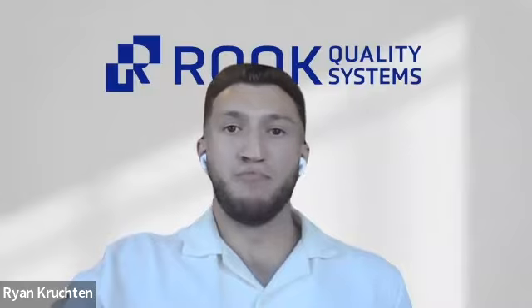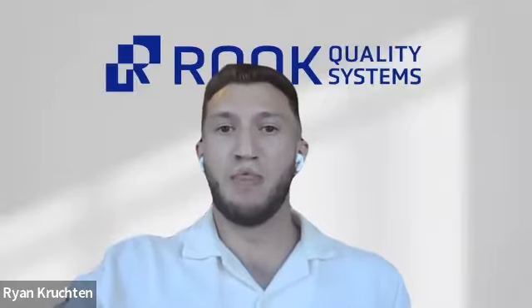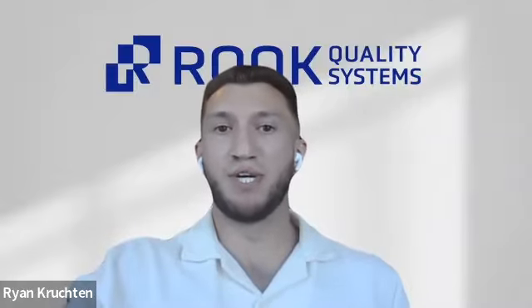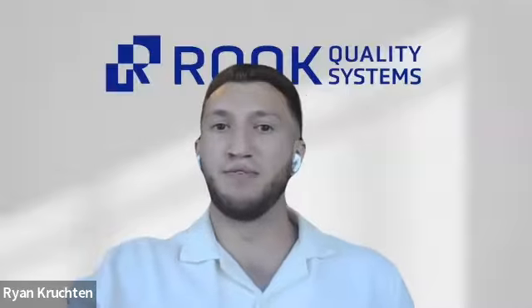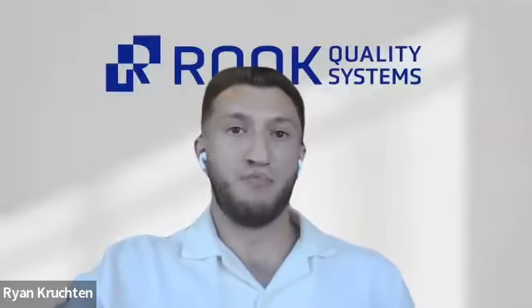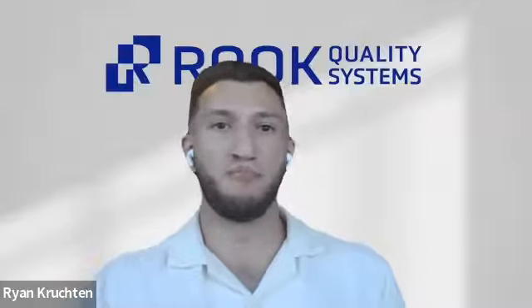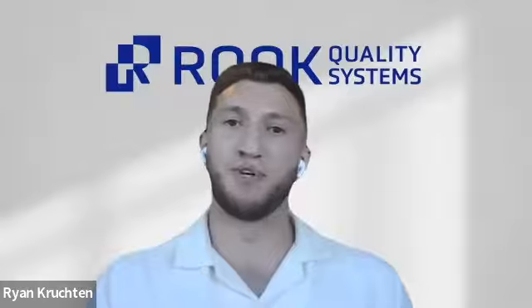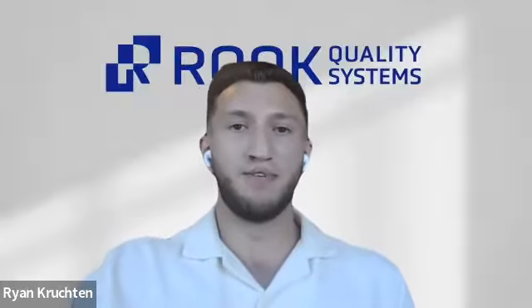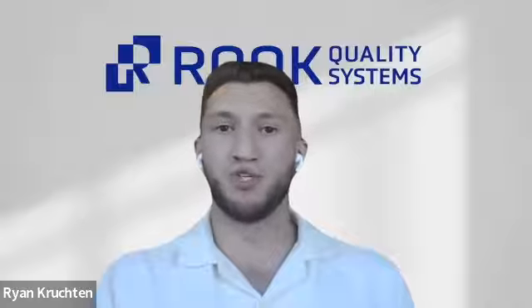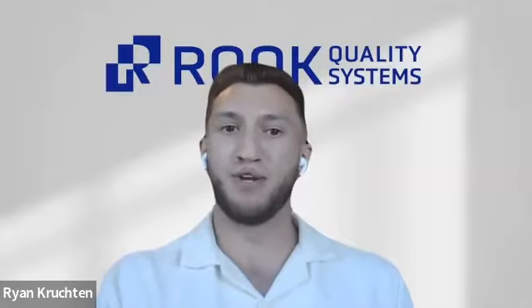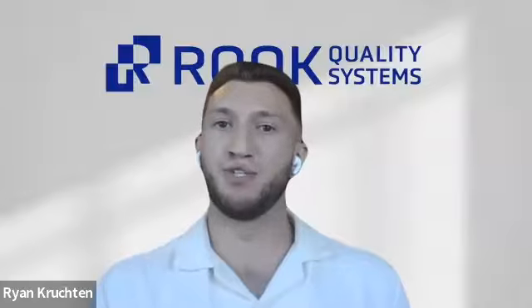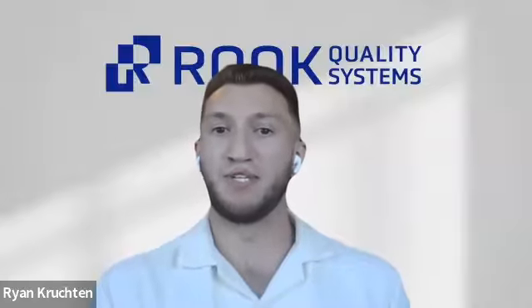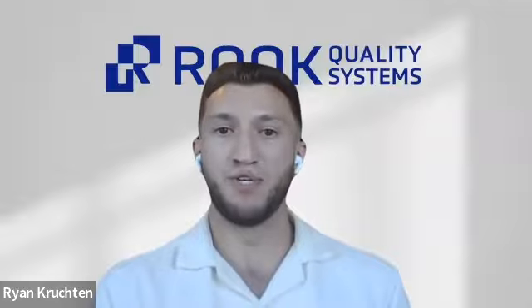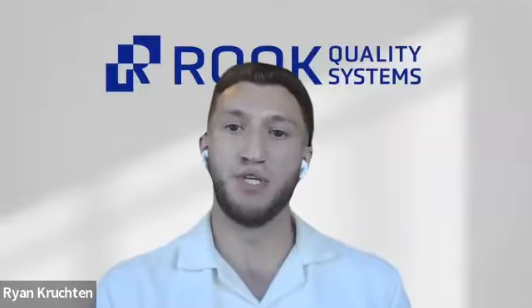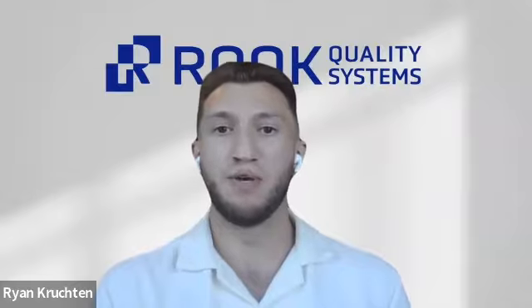Testing is the final check, pre-market, before release, and post-market for updates. Security use case testing, including penetration testing, helps to validate that our defenses were effective. But it's not just about finding a third party to test your product, put them in a room with the product and say, all right, guys, test it, and then tell us when you're done and we'll write the check. We have to internally document those findings and show how they tie into the risk management strategy and process in our organization. So this is an assessment of outcomes, and it's critical for penetration testing, and it can include new design documentation, especially when remediations are required.